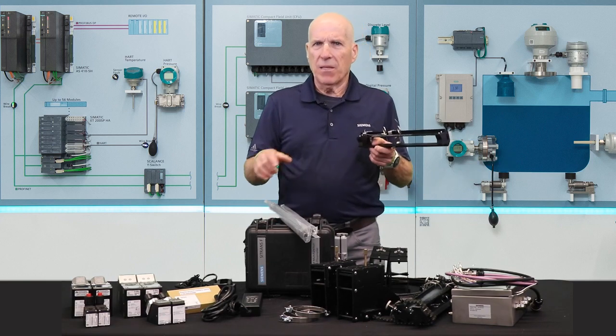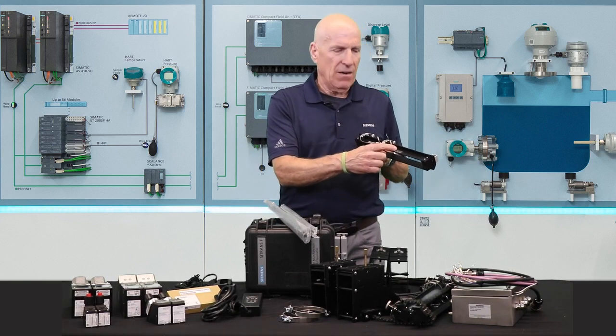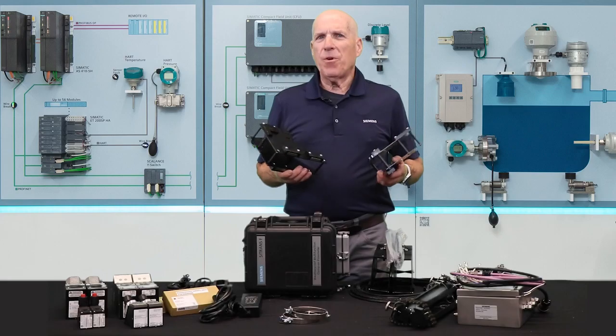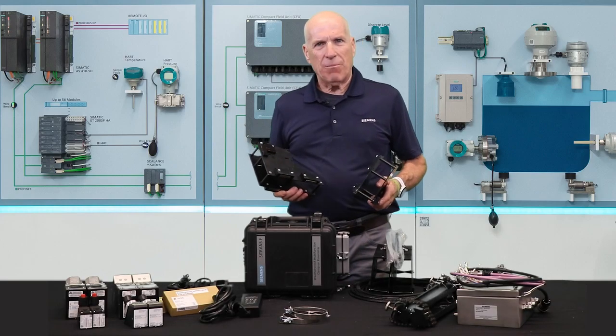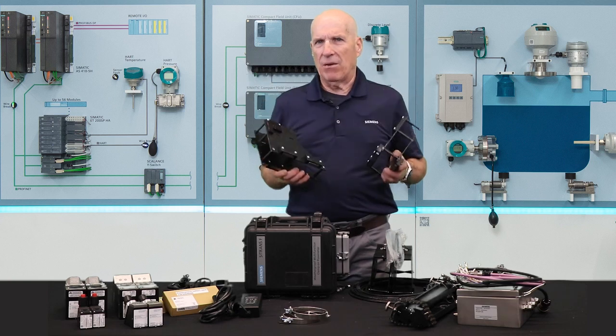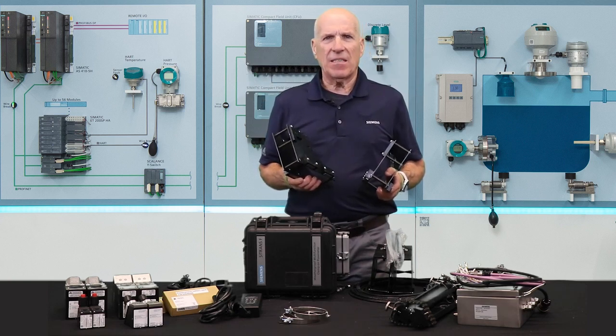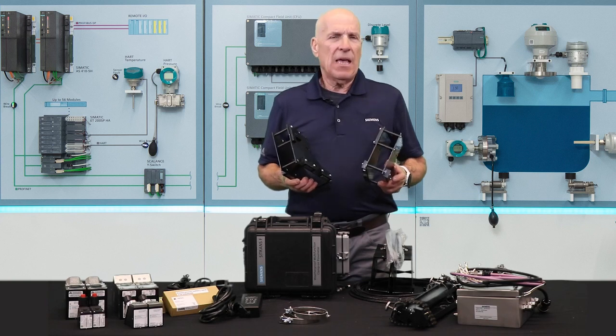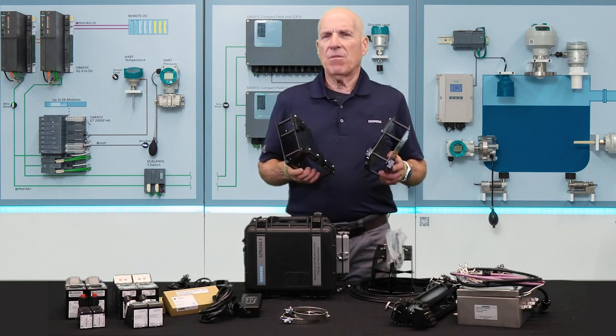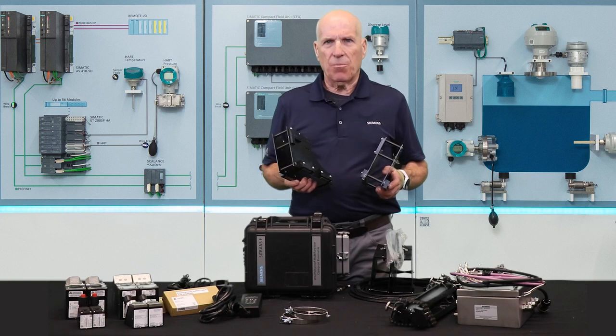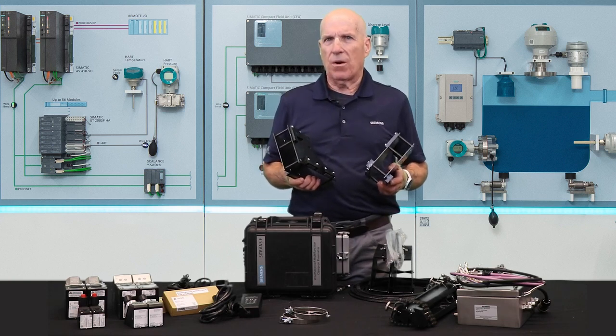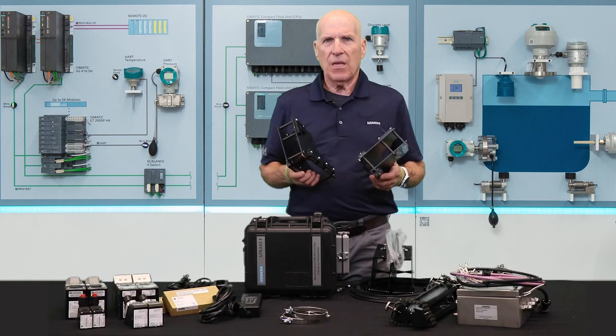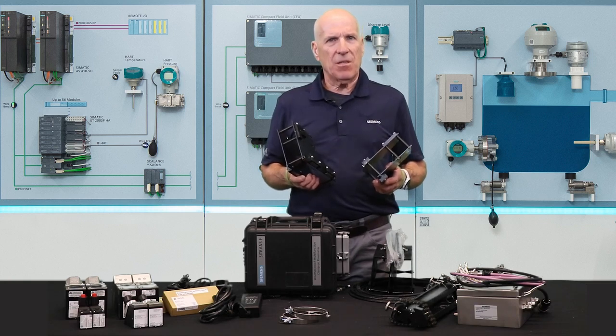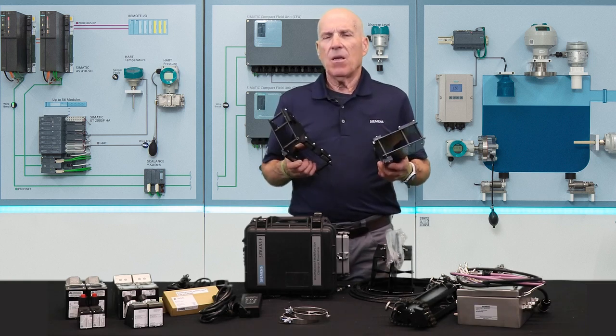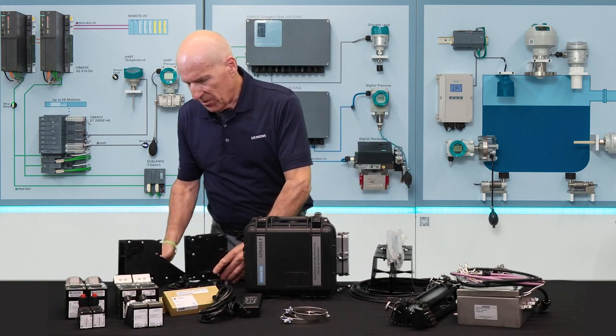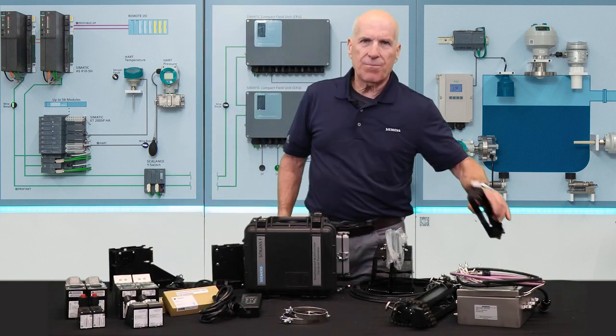Tracks, on the other hand, have built-in mounting positions identified on the side rails. As previously mentioned, my system came with a check metering kit, so I received magnetic mounting frames which can accommodate any size C, D, or E sensor, along with a spacer bar to mount to the pipe. Additionally, mounting chains were supplied for use on pipes where magnets won't work, such as plastic or stainless. In such cases, the frames can be attached to the pipe using only chains. For small diameter pipes, I also received a set of mounting tracks.